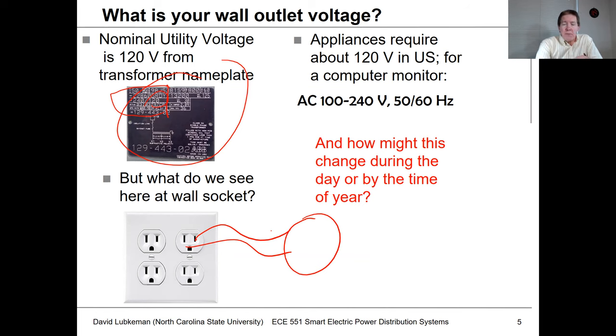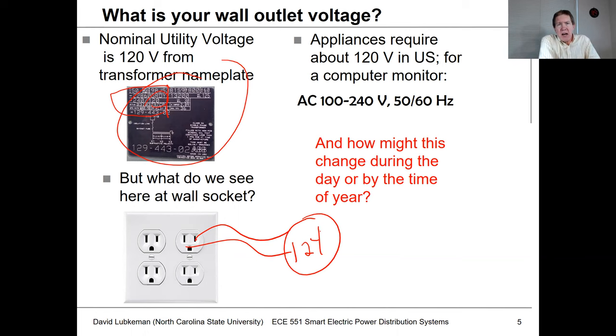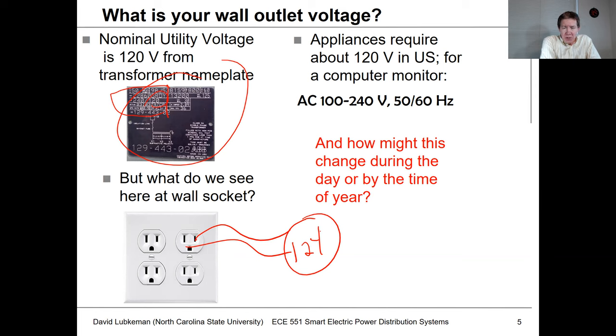I took a measurement while recording and saw a voltage of 124 volts, which is probably a little bit on the high side, but not atypical. A lot of times if you were going to go to different residential sites, you'd probably see voltages more around 122 volts. Utilities tend to keep it a little bit higher to account for drop you might have under high loading conditions.